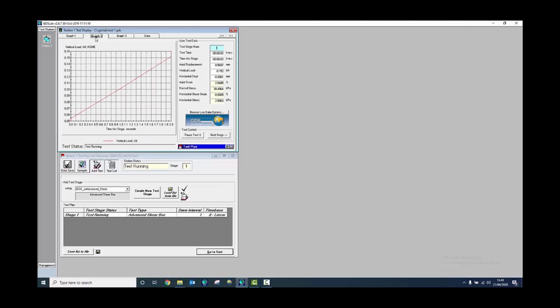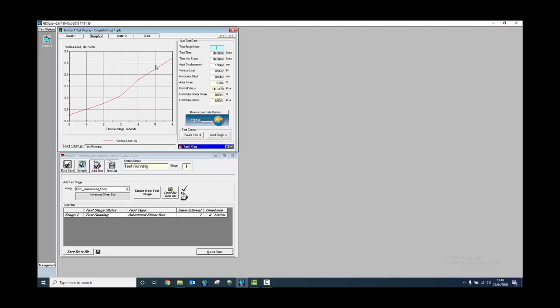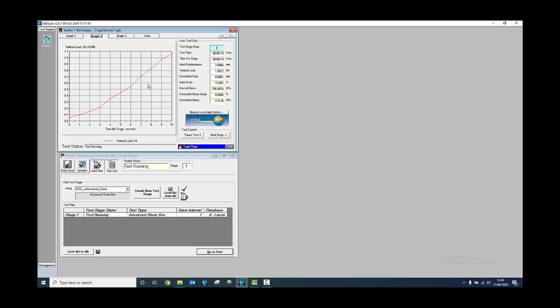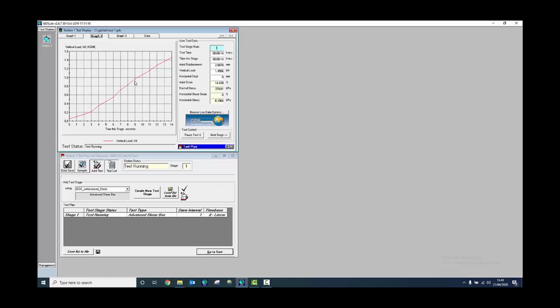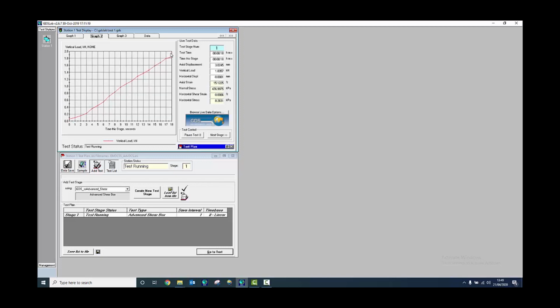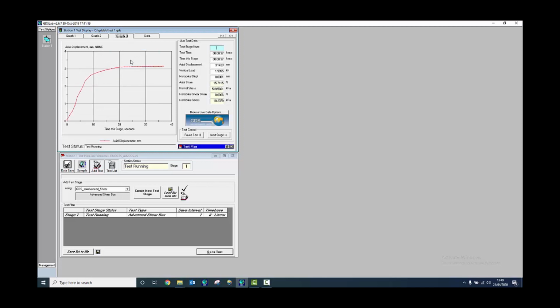If I change the graph 2, you'll see that my vertical load is increasing. Set it to go to 2 kilonewtons. As you can see, the software is maintaining the 2 kilonewton docking force. Look at graph number 3, which is our axial displacement. We can also check the value over here. We'll just give it a little bit of time to completely settle at the new stress.